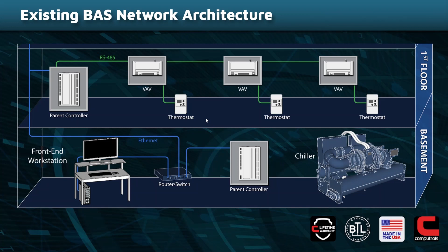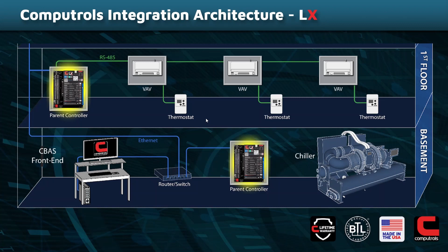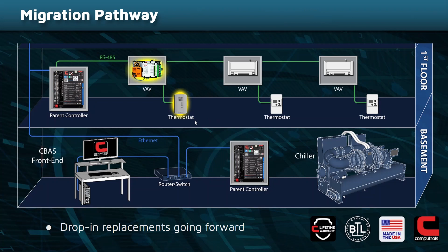Let's recap what an existing BAS looks like. You have a front-end PC, Cat5 Ethernet to a parent controller - if you're familiar with Johnson Controls, it might be an NAE or BCU type topology. Then from there, twisted pair RS-485 goes out to the floor. When we integrate, we can replace that front end, get rid of the old existing software, and migrate to ours. We can often integrate to those parent controllers or possibly replace them depending on the site's needs. When things fail, we can replace it with our controller, either in line with the VAV using a supported protocol, or with the Uni connecting back to the front-end PC over Wi-Fi. There's no magic bullet for each building - every challenge is unique, and the takeaway is that Computrols has a flexible enough approach to meet those needs, not a one-size-fits-all approach.